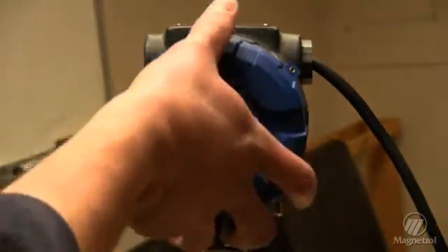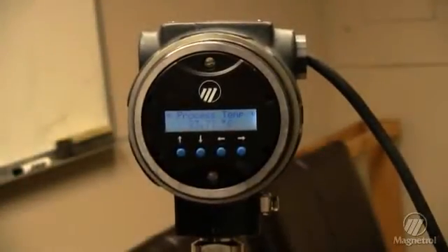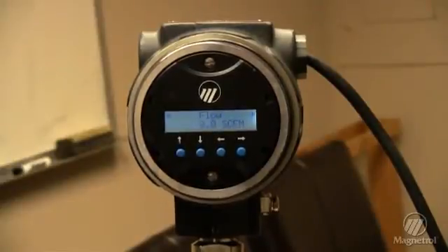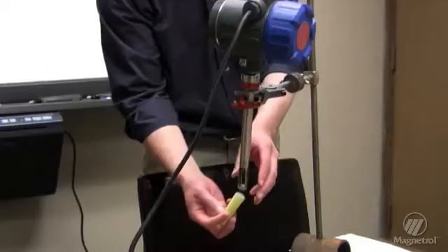The first test is a low flow validation. During the test, the heater power is set and the temperature difference between the RTDs is measured. To do this, wrap the sensor tip so no air flow can flow past the pins.